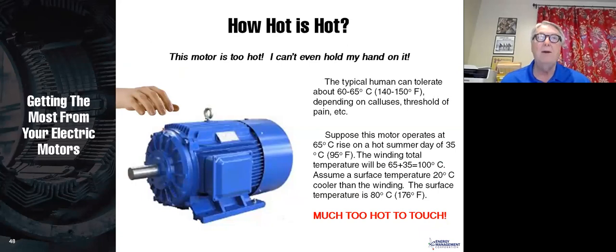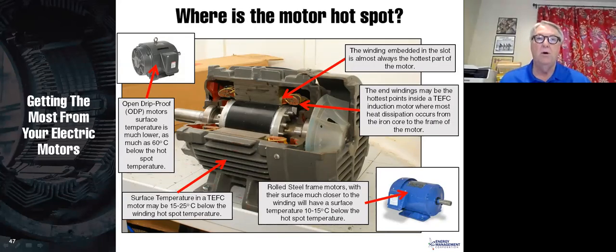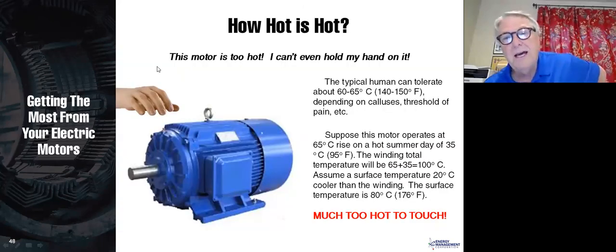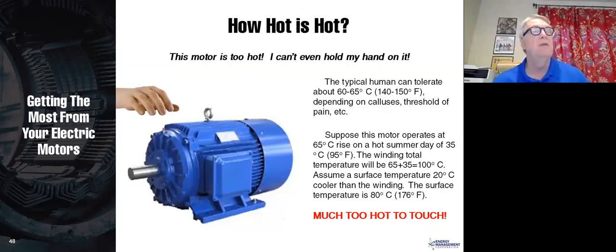Now, my rule of thumb for many, many years has been put your hand on the motor. If you can hold your hand on the motor for 3 seconds, then the motor is not too hot. Other than this open drip proof cast iron motor that I showed you before, that's still a pretty good rule of thumb. But if you can't keep your hand on the outside of the motor for 3 seconds, the motor might still not be too hot. So let's take a look.